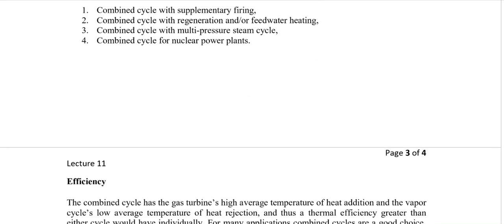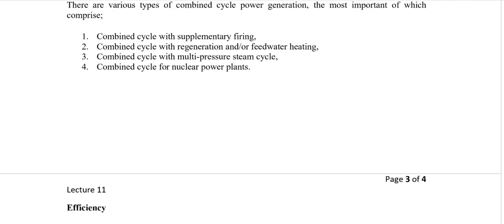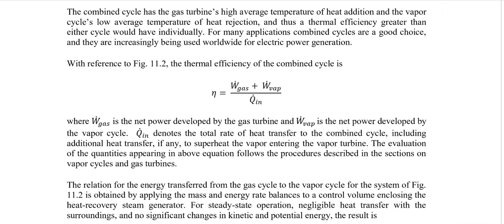With reference to figure 11.2, we have the combination of two cycles — the gas cycle and the vapor cycle. The efficiency depends on the work output of both cycles. There is only one heat addition: in the combustion chamber of the gas cycle, so Q-in is from one source. For mass and energy balance, the gas enters the HRSG at point 4 and leaves at point 5, so the energy transferred is H4 minus H5.